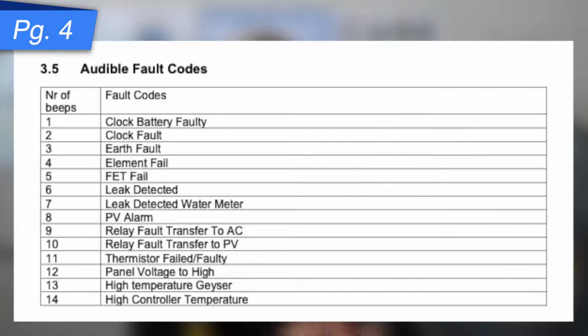And I must just mention, with the Wi-Fi app, it makes it a lot easier. But if you don't have the Wi-Fi app and you choose not to go that route, the Audible fault codes will be able to assist you. So if it's beeping 4 times, it's going to beep, beep, beep, beep, then there'll be a short break, and then 4 times again. So when you're installing, look out for the break and count the beeps, and that's going to indicate to us what the fault is. 3.5 indicates the typical fault codes.